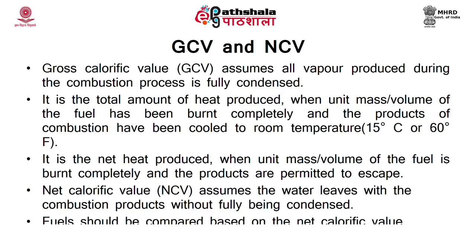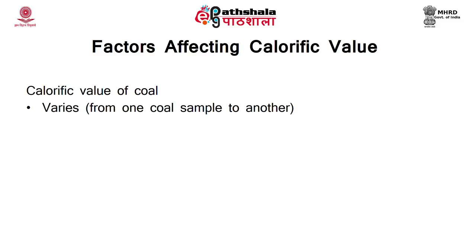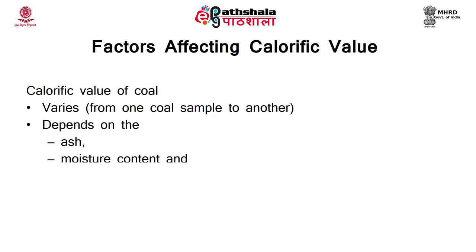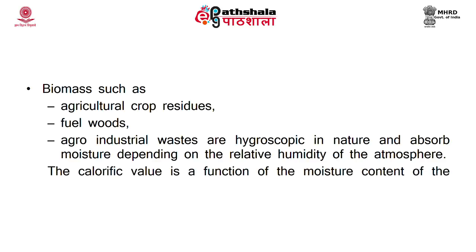Fuels are mainly compared based on the net calorific value rather than GCV. Factors affecting calorific value: it varies with the substrate or fuel sample. For example, calorific value of coal varies depending on ash content, moisture content, and type of coal. The calorific value of fuel oils are more or less consistent. Biomass such as agricultural crop residue, fuel wood, and agro-industrial waste are hygroscopic and absorb moisture depending on relative humidity, so their calorific value varies as a function of moisture content.